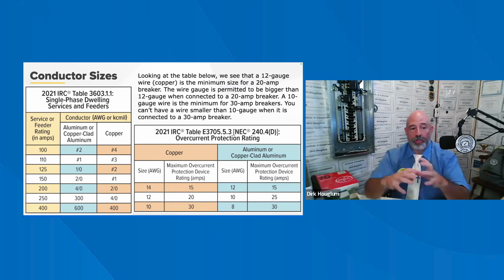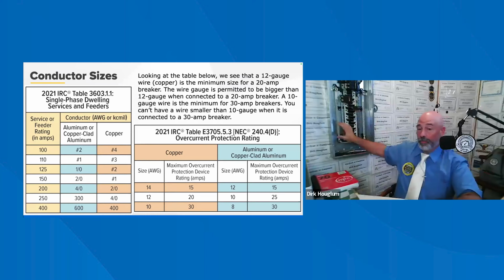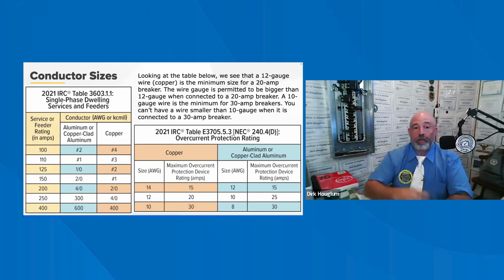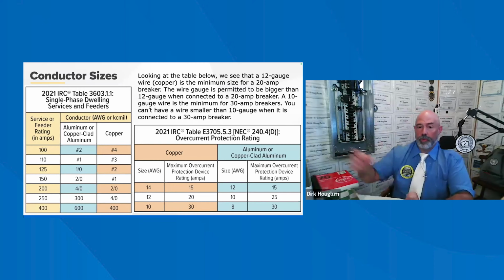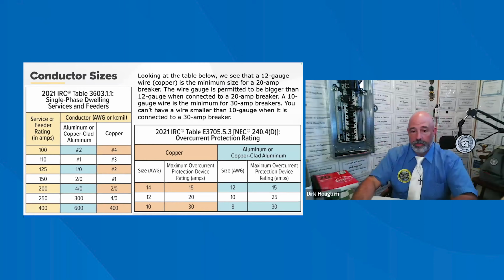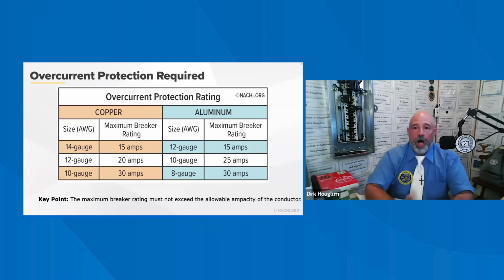So you want to make sure that you're looking at both of those when you're doing electrical inspections. When you're taking that off, you're looking at the numbers, making sure that things look good. When I first started in electrical, somebody gave me the good idea to go to one of these home improvement stores and get some clippings of the different sizes, so you have them in your pouches. Or you can buy the gauge tool that will tell you. So it's a couple of good things to do. All ungrounded branch circuit and feeder conductors must be protected by an overcurrent device.